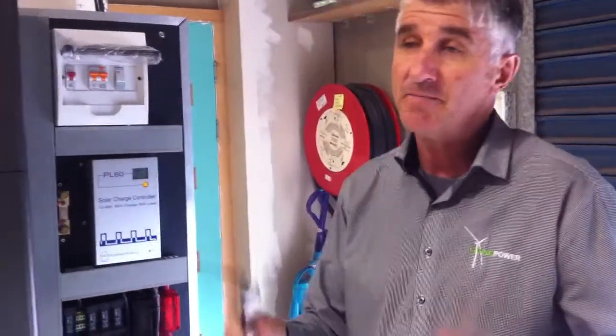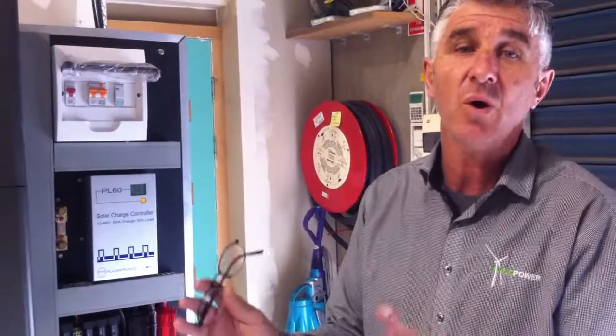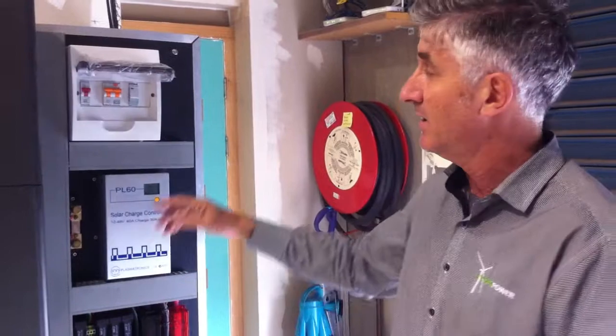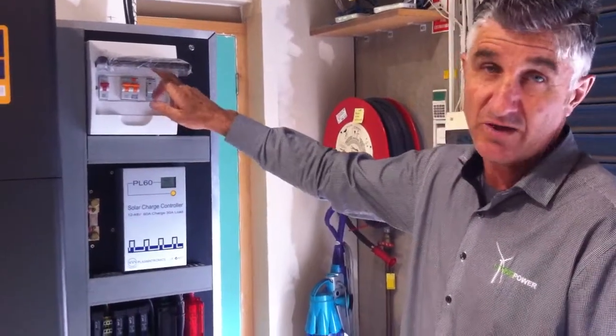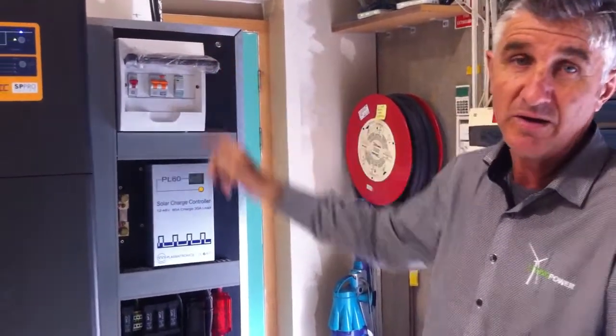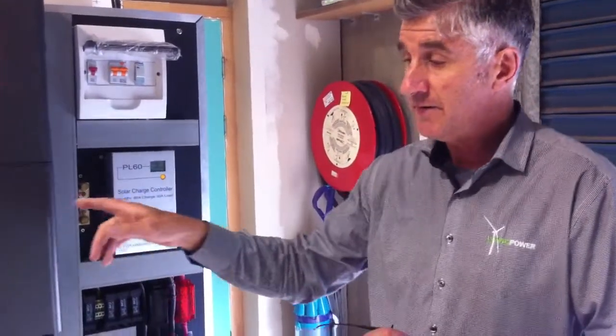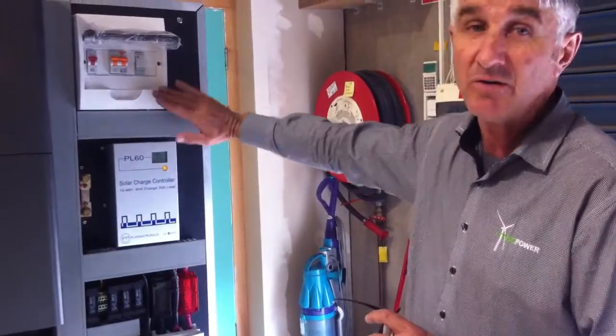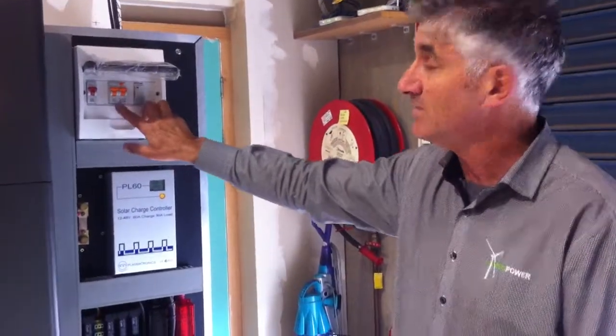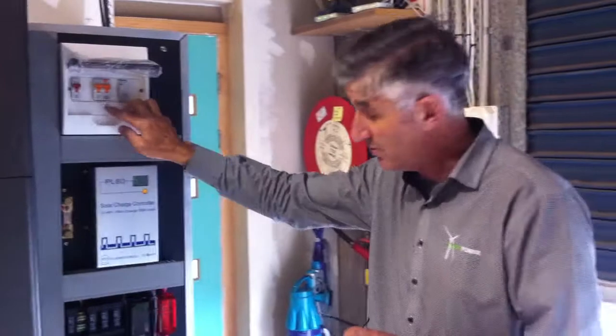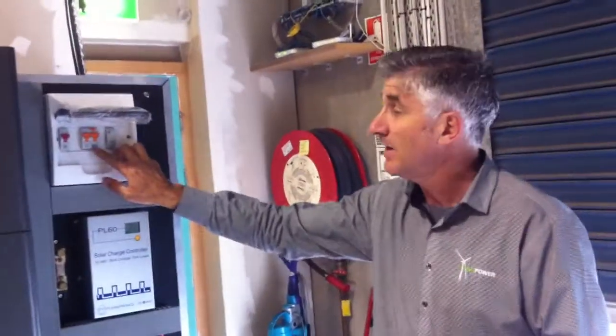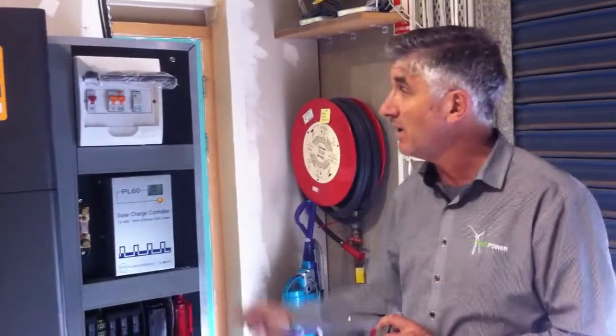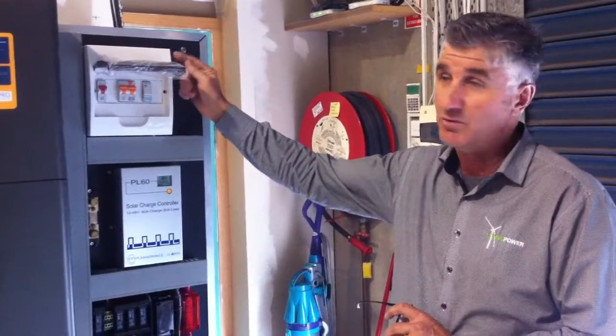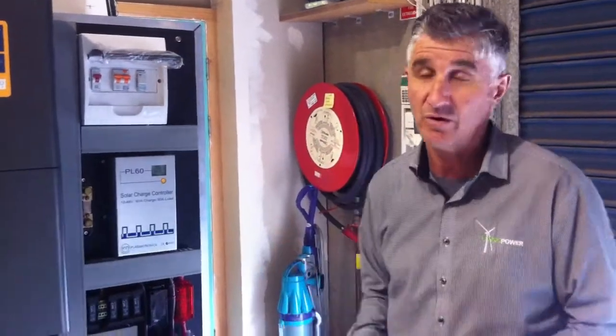This means if your electrician has wired up your place, he needs to have an earth stake in somewhere, so he'll just run an earth link, an earth cable, from our earth bar to the earth bar in the localised switchboard. If this is a totally standalone setup and the only switchboard on the property, you'll need to make sure we've given you an earth stake, which you'll drive into the ground and connect your earth cable up to our earth bar. That'll give you a good earth.